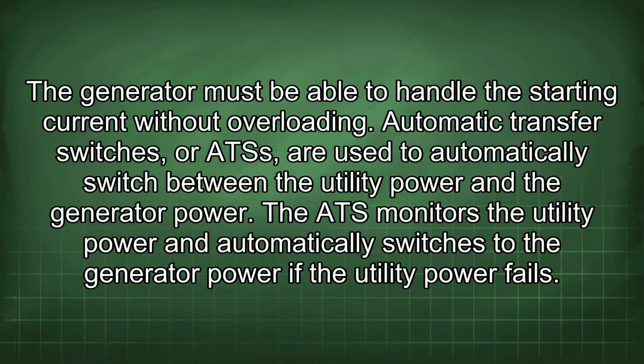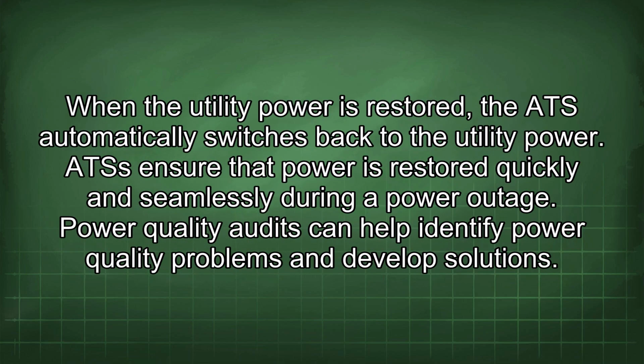The ATS monitors the utility power and automatically switches to the generator power if the utility power fails. When the utility power is restored, the ATS automatically switches back to the utility power. ATS ensure that power is restored quickly and seamlessly during a power outage. Power quality audits can help identify power quality problems and develop solutions.